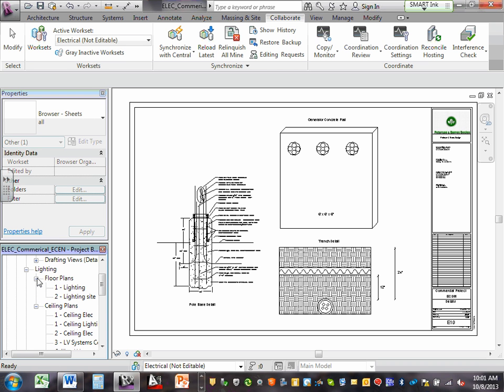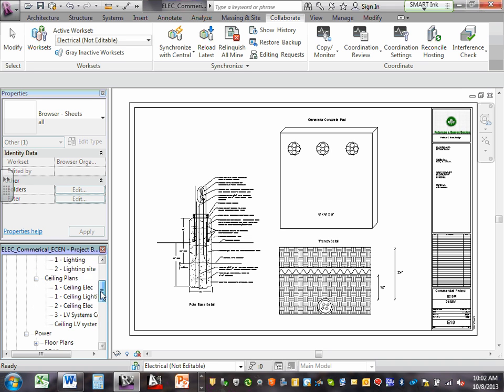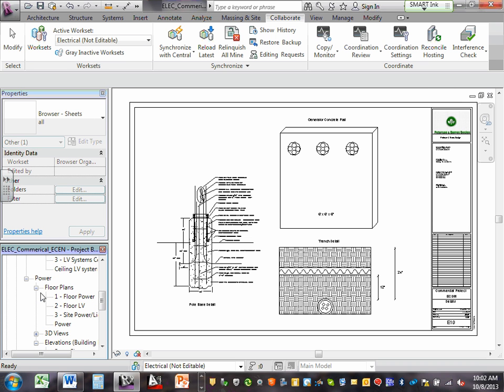Why do we need a ceiling view and a floor view for lighting? Where do you put your lights? In the ceiling. Where do you put your receptacles? About the floor — typically four feet above the floor. So you need to see receptacles on the floor view and lights on the ceiling view. That's why they give you two views. For power, they give you only floor plan, because most power equipment sits on or near the floor.